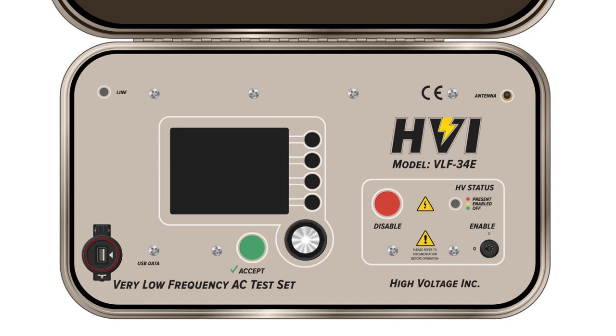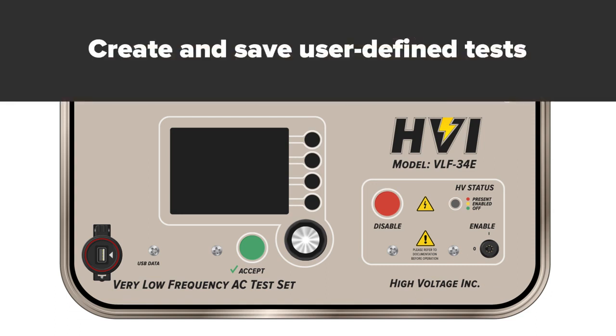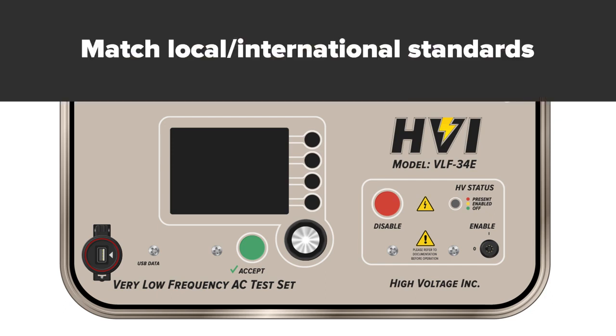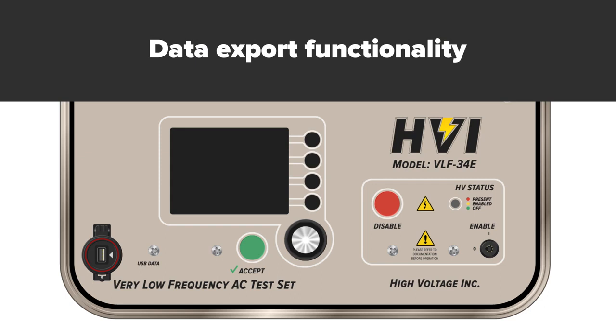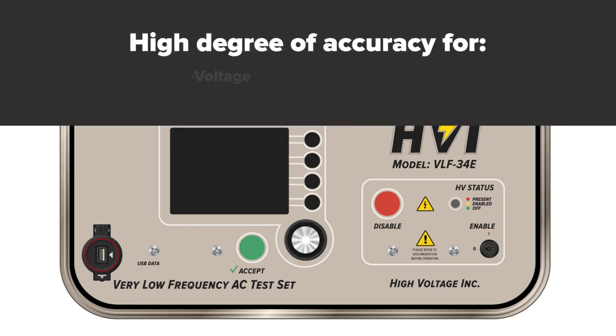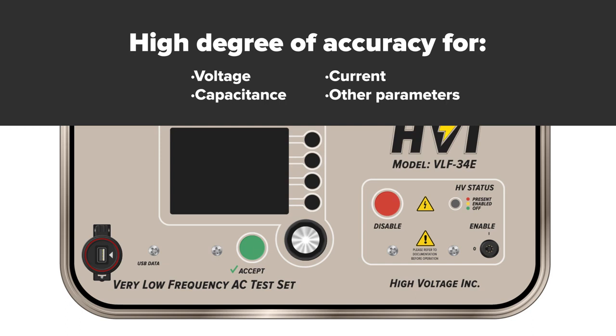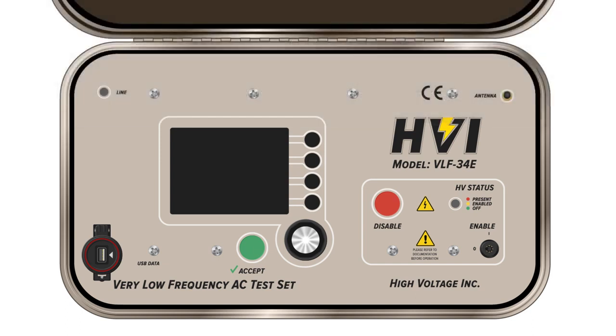The E-Series is designed to test, save, and export results for VLF high-voltage tests, typically withstand or maintenance tests for medium to high-voltage power cables. They provide a high degree of accuracy for measuring voltage, current, capacitance, and other parameters. Electrical testing professionals can test directly from a manual mode, or create predefined testing profiles or sequences.